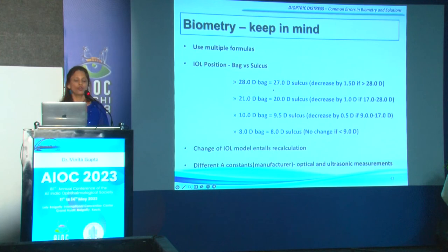Practically, you can remember it by the rule of 9. Especially if you're changing your IOL model, you have to recalculate. You cannot use a different company's IOL with the same calculations and the same power. Different A constants must also be remembered if you have done measurements from an optical or an ultrasonic biometer. If your IOL package doesn't provide that, ask the company person to give it to you if you're using the same type of IOL for all your patients.